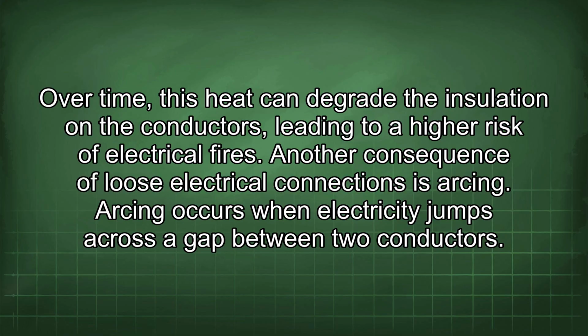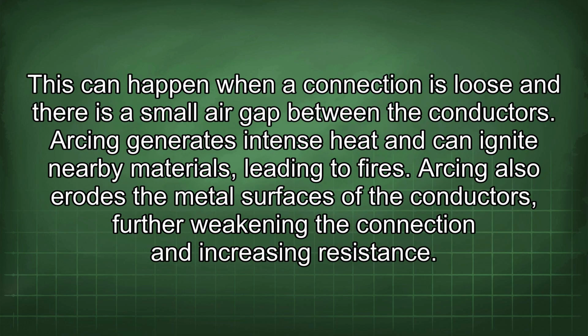Another consequence of loose electrical connections is arcing. Arcing occurs when electricity jumps across the gap between two conductors. This can happen when a connection is loose and there is a small air gap between the conductors. Arcing generates intense heat and can ignite nearby materials, leading to fires. Arcing also erodes the metal surfaces of the conductors, further weakening the connection and increasing resistance.